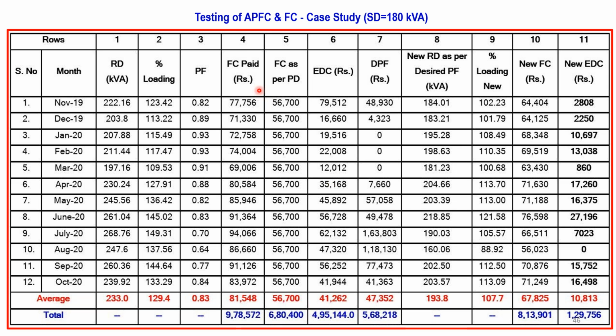Similarly, for the fixed cost paid by the company, if they maintain the demand within the limit, then automatically there is almost 2 lakh rupees of difference. Overall, it is going to be around 12 to 14 lakh rupees of difference, the excess paid by the company for 1 year. Now if the power factor is maintained at 0.99 as the desired power factor, then the new value of the fixed cost and the new value of the EDC is going to be available here.